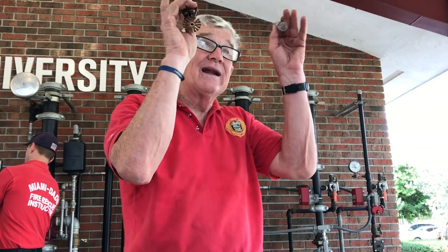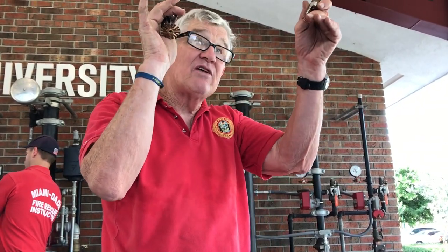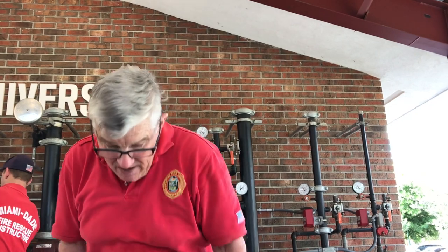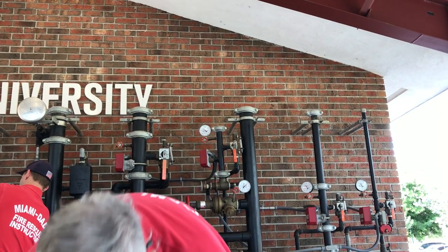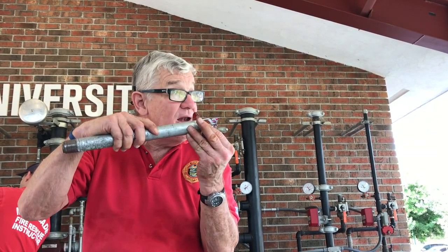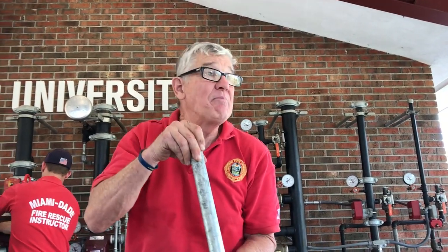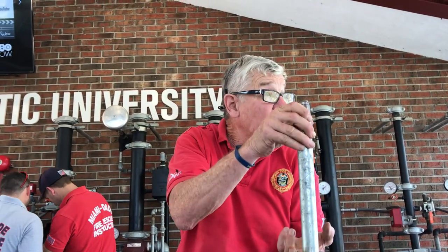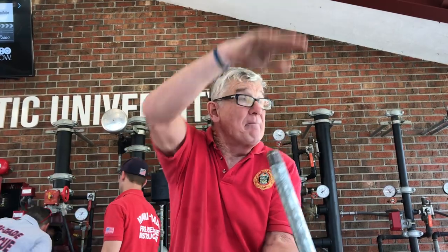So, little guy, residential, big guy, and systems are rated in gallons per minute per square foot, discharge density. Simply put, you're gonna have a greater discharge density in terms of gallons per minute per foot in a tire warehouse than you will in your apartment, okay? So, we've talked about the sidewall head, and we talked about the dry pendant head that could go down into a freezing space if this is ambient above.